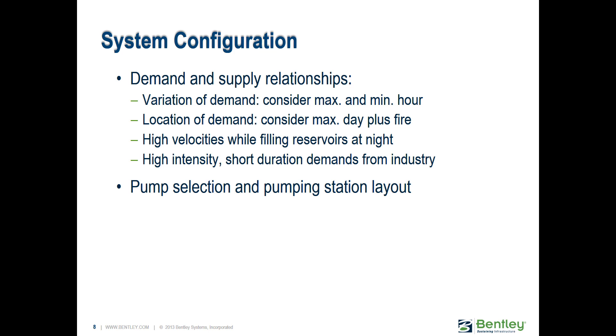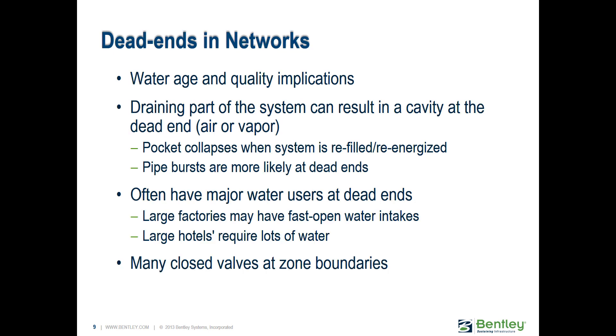Pump selection and pump station layout are important considerations. Dead ends in networks are a topological concern — they can be a water age issue (sometimes why you need to flush the system) and also impact the transient response through wave reflections. If part of the system is drained, that can result in a pocket of air at the dead end. Those pockets could collapse when the system is refilled — a question that comes up is what happens when you refill empty pipes.